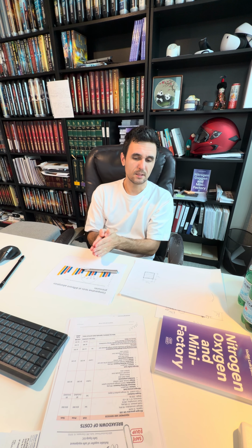It's important to understand how much flow it gives. We can easily calculate it by taking a look at the data sheets of the air compressor, or just by knowing the model. Even if we don't know the model, we can see the motor inside of it, and usually for a certain amount of kilowatts or horsepower of the motor, we can calculate how much flow it gives us.